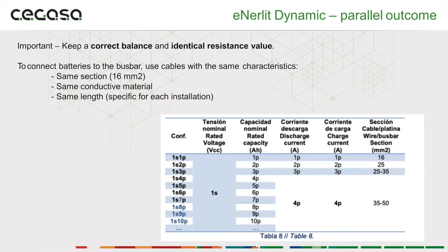When talking about correct balance, it's very important to equalize all the components of the system. If you're connecting every battery to the busbar, use the same type of cable with the same conductive material, and the length is quite important, because we're looking to have the same resistance on each battery. One mistake we've seen is different batteries having different cable lengths, offering slightly less resistance, and causing imbalance in the system.